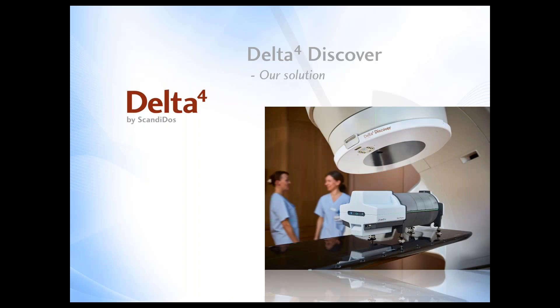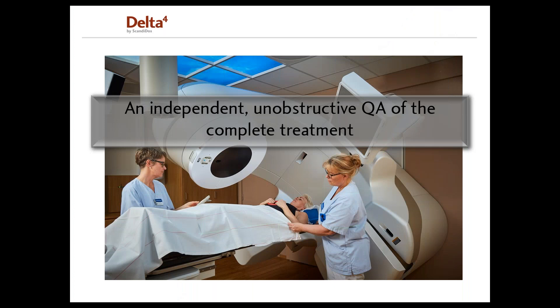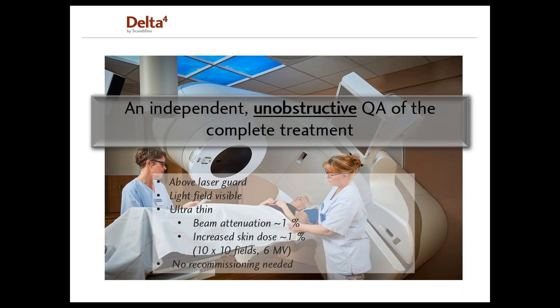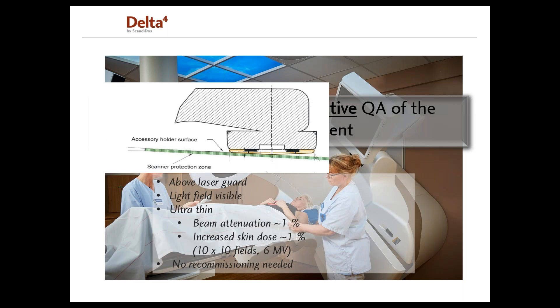Let me present our solution, the Delta4 Discover. With it, you get an independent, unobstructive QA of the complete treatment. The Delta4 Discover is completely independent from the accelerator — the hardware and software are separate from those on the linac, and it is not based on any log files from the linear accelerator. Unobstructive means the Delta4 sits only six millimeters from the guidance pin of the accelerator and actually passes above the laser guard of a Varian accelerator.